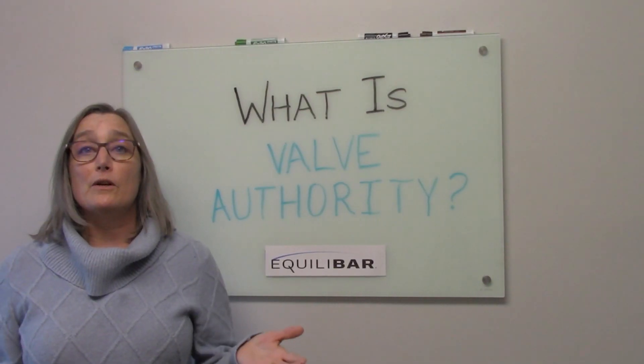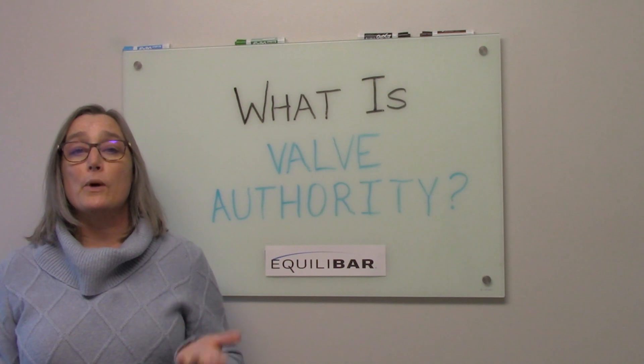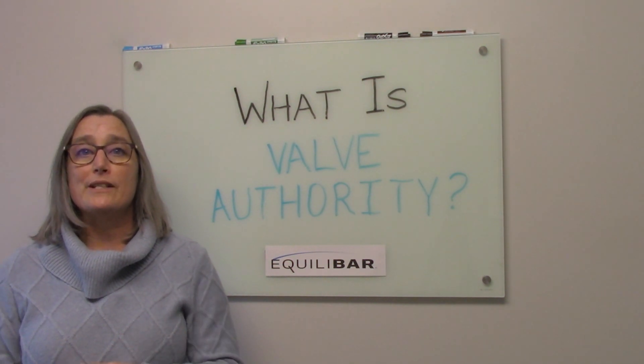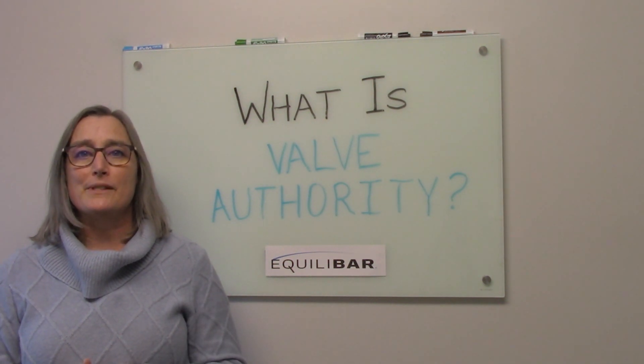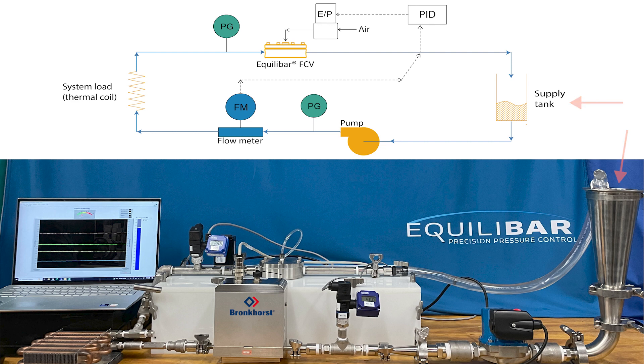Theory is great, but let's take a look at the Equilibar control valve controlling through a wide operating window with valve authority down below 5 percent. In our setup, a centrifugal water pump capable of about 10 psi output, typical of hydronic systems, pumps water from a supply tank through the system. As the flow increases, the output pressure decays as predicted by a classic pump curve.